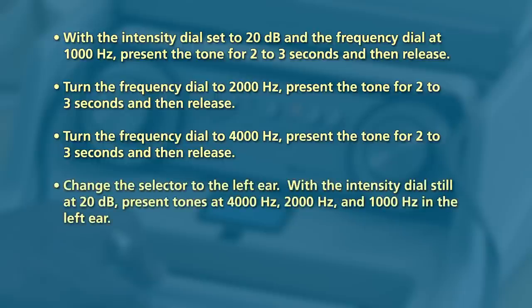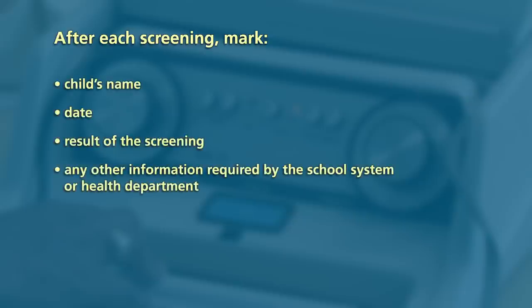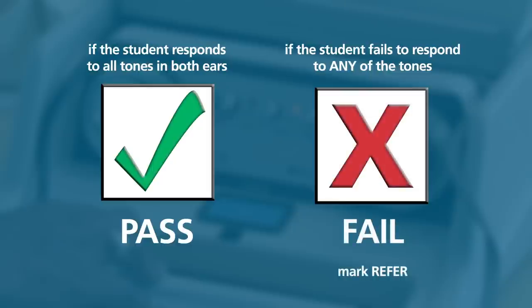Change the selector to the left ear. With the intensity dial still at 20 dB, present tones at 4,000 Hz, 2,000 Hz, and 1,000 Hz in the left ear. After each screening, the screener should mark the child's name, the date, the result of the screening, and any other information required by the school system and/or health department. If the student responds to all of the tones in both ears, they have passed the screening. If the student fails to respond to any of the tones — even if they miss only one tone — they have failed the screening. Mark 'refer' on the response form if they do not respond to all of the tones.